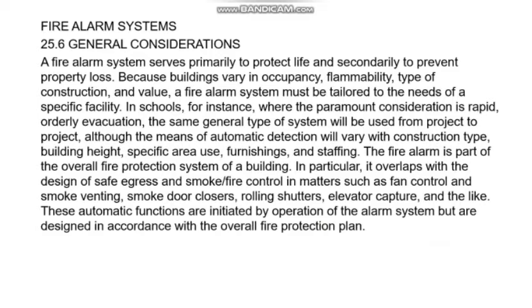In particular, it overlaps with the design of safe egress and smoke or fire control in matters such as fan control and smoke venting, smoke doors, smoke door closers, rolling shutters, elevator capture, and the like. These automatic functions are initiated by operation of the alarm system but are designed in accordance with the overall fire protection plan.